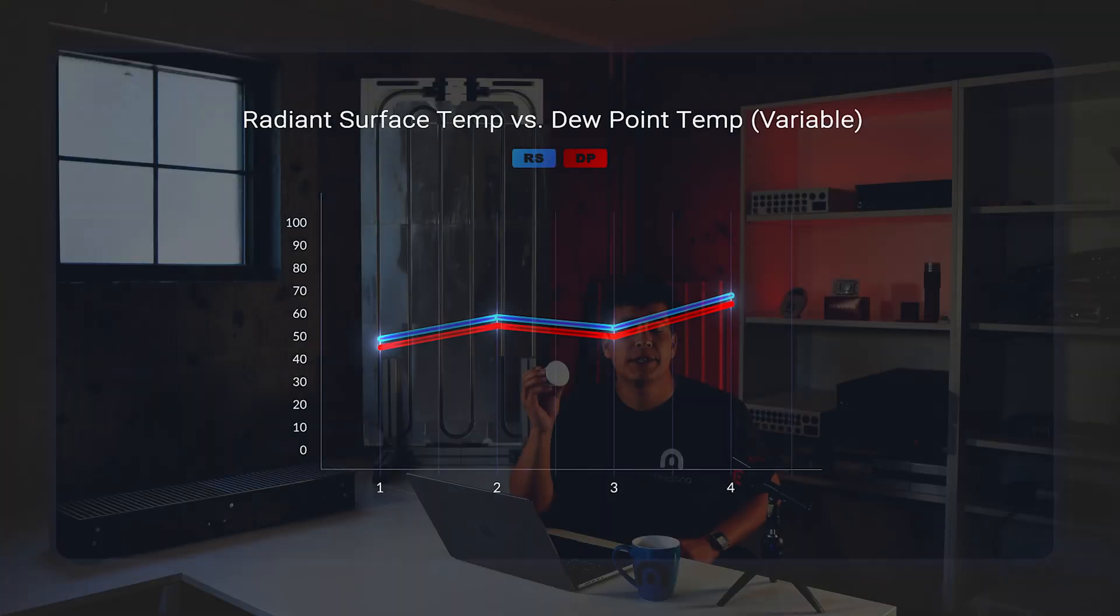Now our mSenseRoom comfort sensor monitors a few things. First, we have operative temperature, which is similar to air temperature but takes into account the radiant temperature. This gives us a better idea of what our skin receptors would actually feel. It also monitors relative humidity.